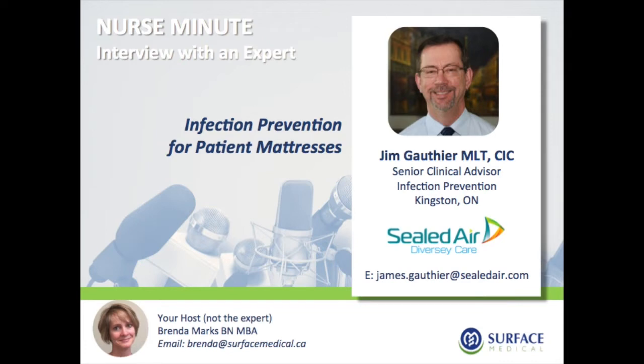The mattress obviously should be stripped down and inspected before any cleaning to make sure that there are no breaches in it or holes, rips, or cuts. If holes, rips, or cuts are discovered, you should check the integrity of the foam or the lining inside the mattress cover to make sure that no body fluids or other solutions have made it into that part of the mattress.